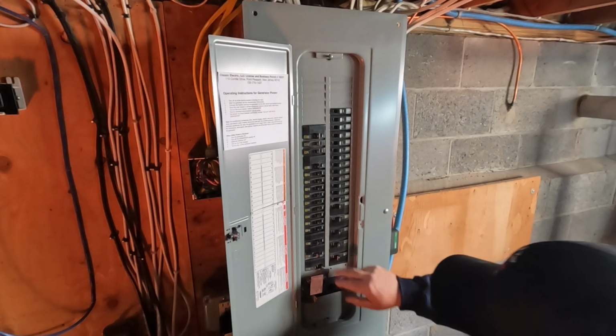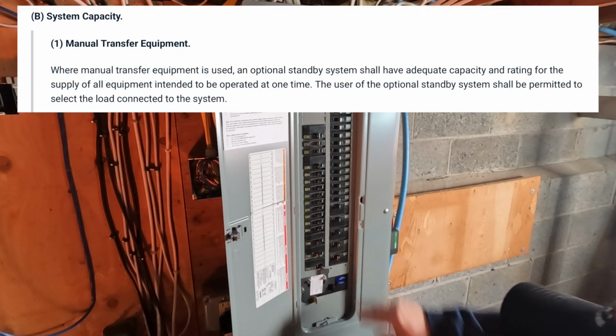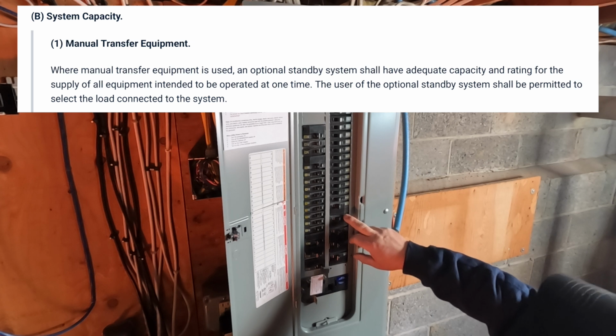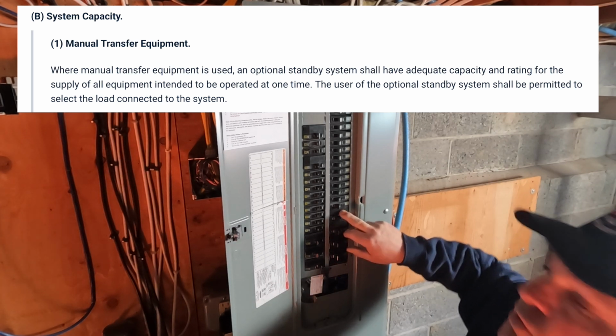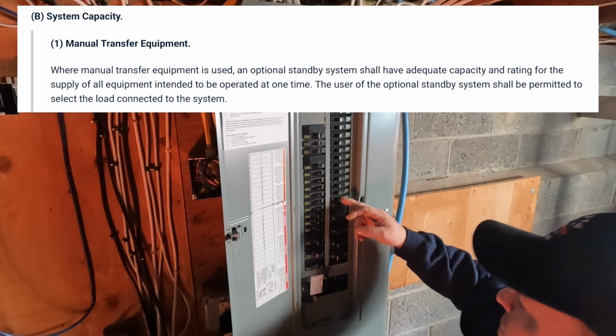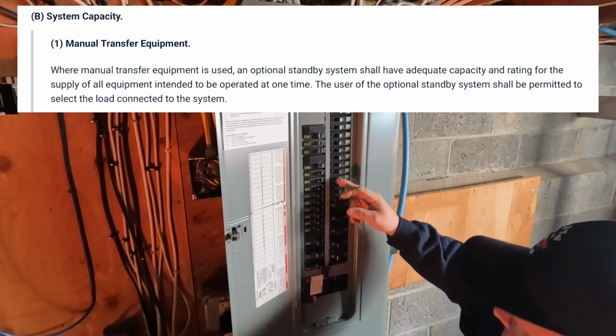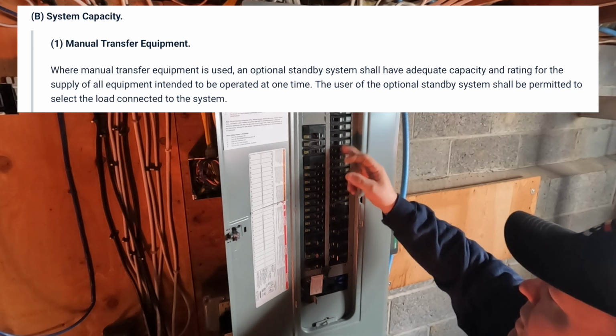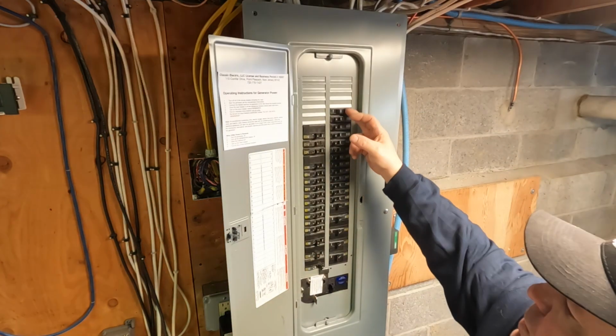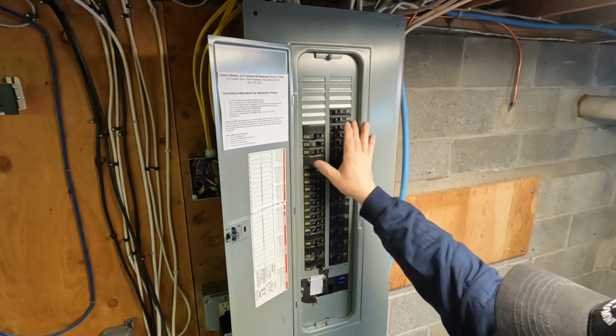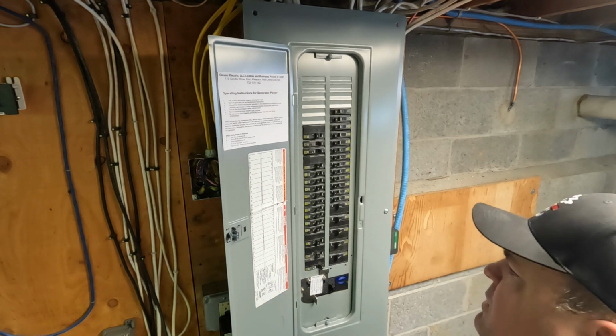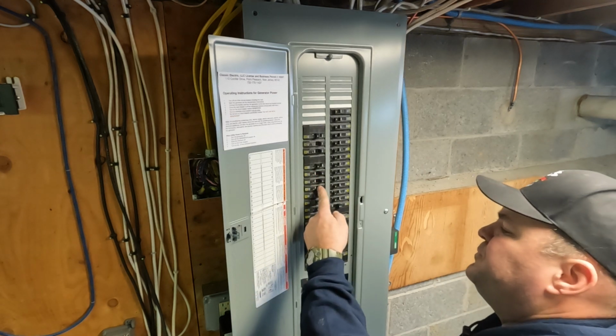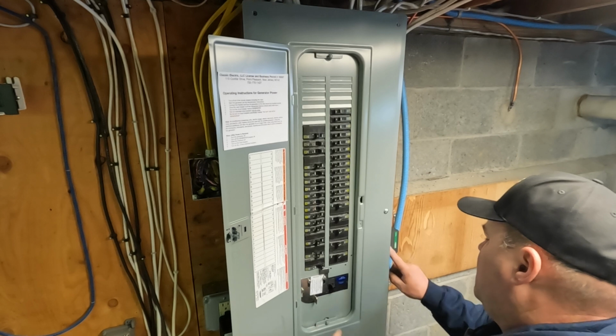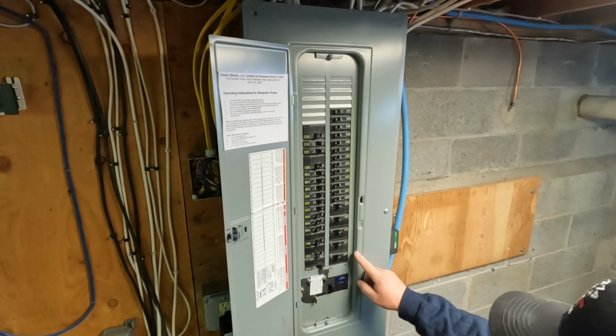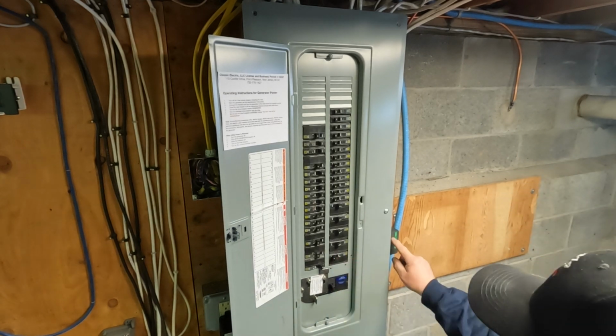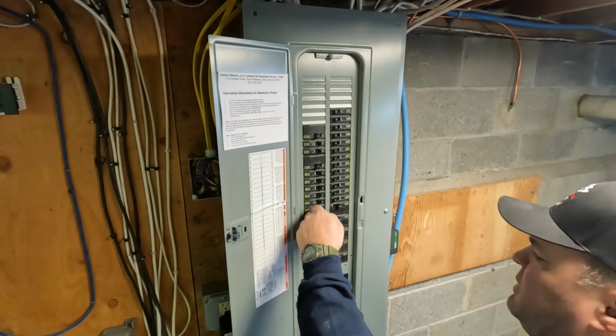Now the idea is not to turn on any of these 240 volt circuit breakers. They'll be tagged momentarily to not use them during the power outage. But we can turn on the rest of our individual circuit breakers. Right? And all the lights just come back on. We are on generator power right now. And we're going to turn our surge on because that's not drawing any power and that's going to help us should there be a surge.